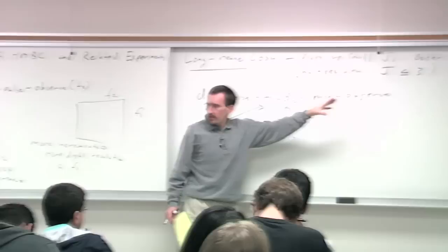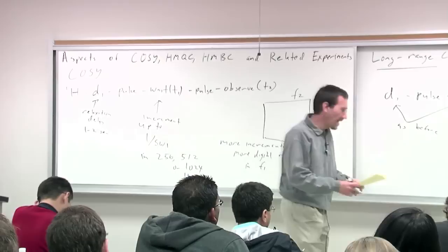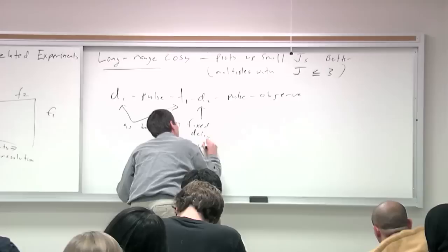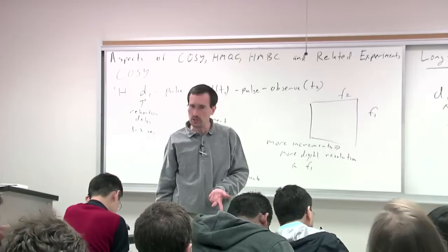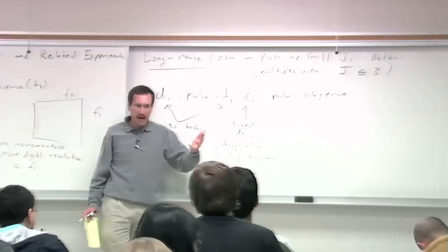A long-range COSY adds an extra fixed delay — D2 — that gives these small J's better visibility. The sequence is D1, pulse, T1 as before, but now you add one more fixed delay D2, then pulse and observe. The fixed delay is typically 100 to 400 milliseconds; longer is better for picking up small J's, but there's a caveat: what's happening during those 100 to 400 milliseconds? Relaxation — so you're losing signal intensity as your magnetization returns to the Z axis.